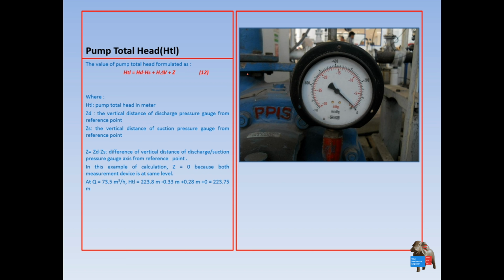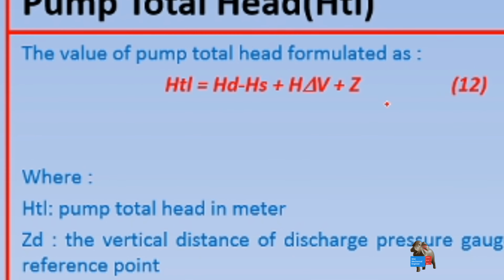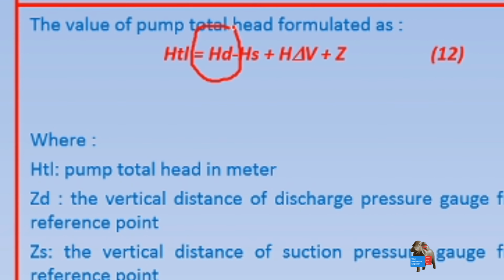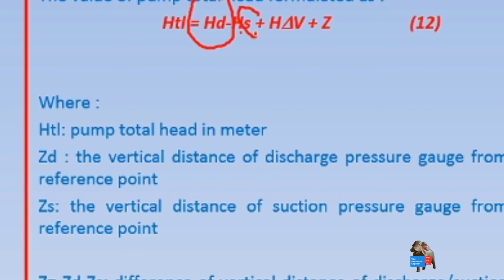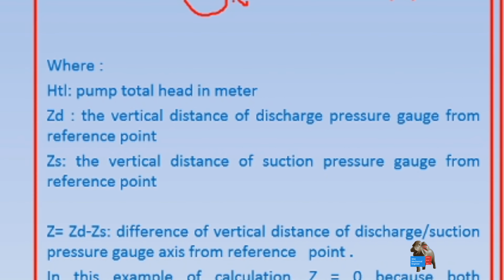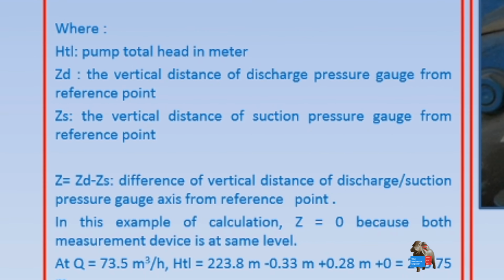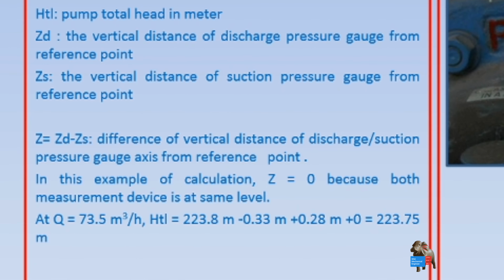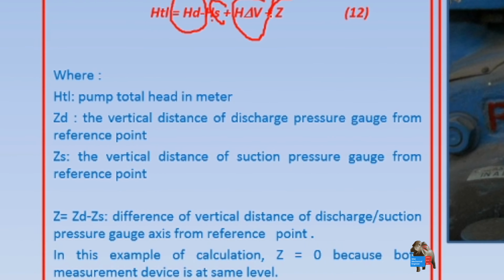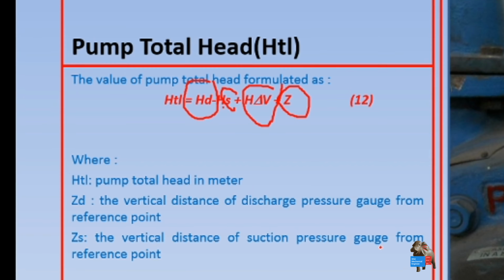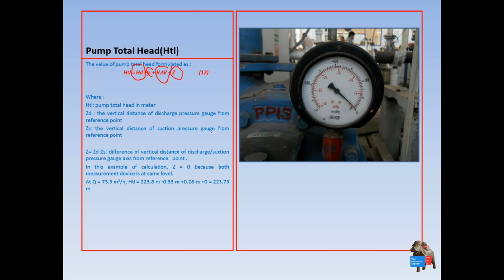And then after that, you have the data. You will need to calculate what you call the pump total head. Pump total head is equal to the head of the discharge minus the head of the suction, plus the delta of the velocity pressure, and delta z. This delta z is the difference of the measurement points at suction and discharge. This is an example of the calculation.